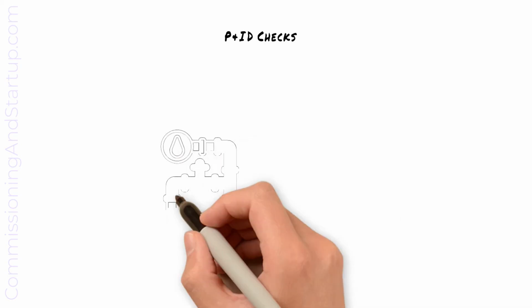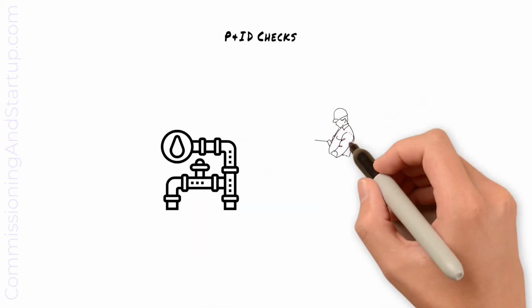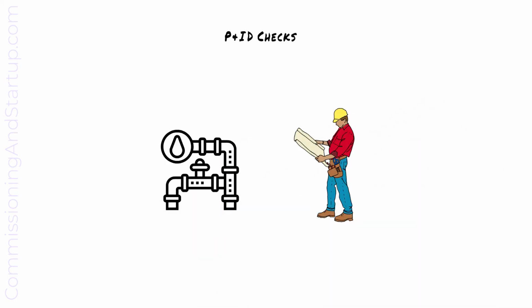At mechanical completion, the construction and commissioning teams will jointly walk the systems to verify that installed equipment matches P&ID drawings. This verification confirms that all piping is installed per the drawing, all valves are installed, and any pressure gauges are correctly in place.